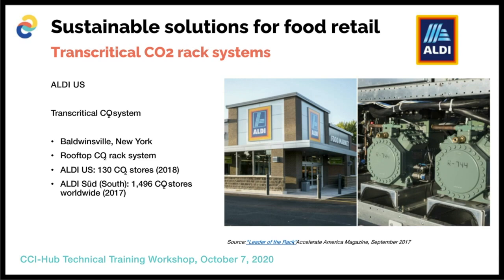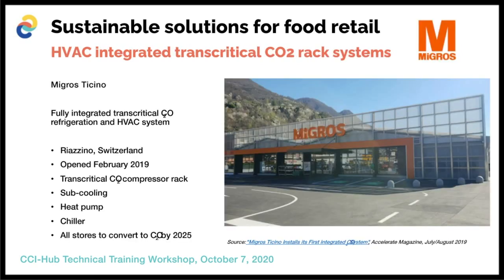Example from Switzerland, again, a CO2 transcritical rack. But as we progressed with the development of the technology, the CO2 transcritical rack has also been used for air conditioning, for providing hot water with the heat reclaim, and for melting of ice in a heat pump configuration. There are many different advancements added to the system. So there was a lot of innovation in this space. Migros plans to use CO2 in all of their stores by 2025.